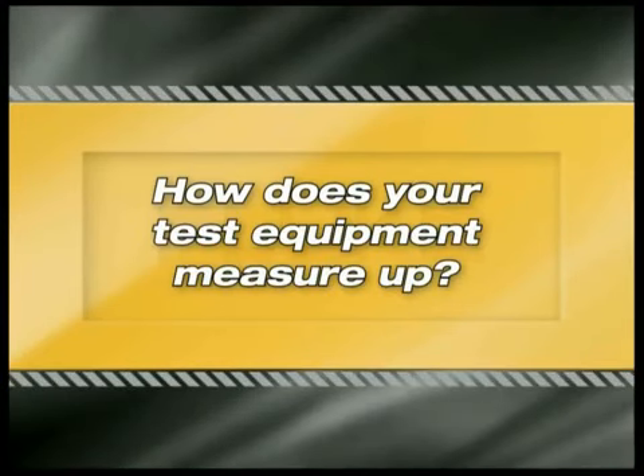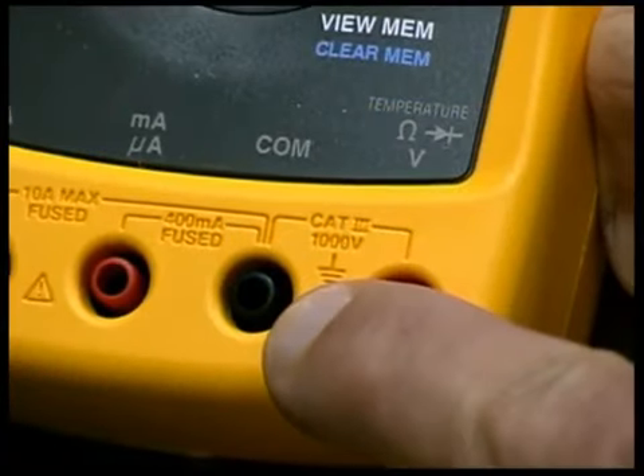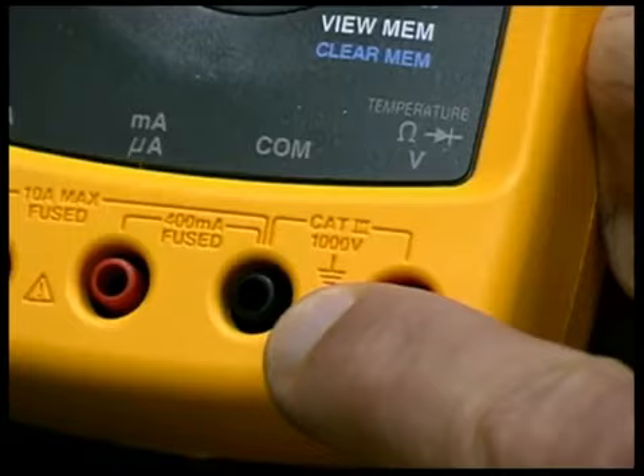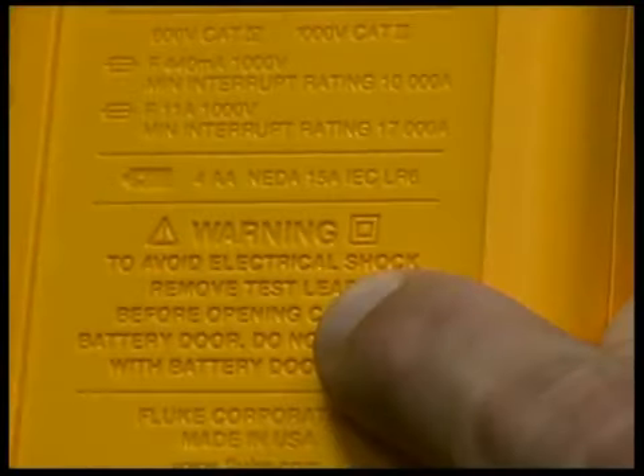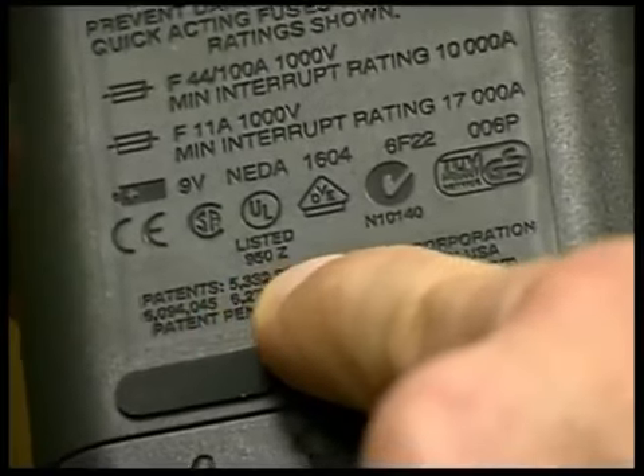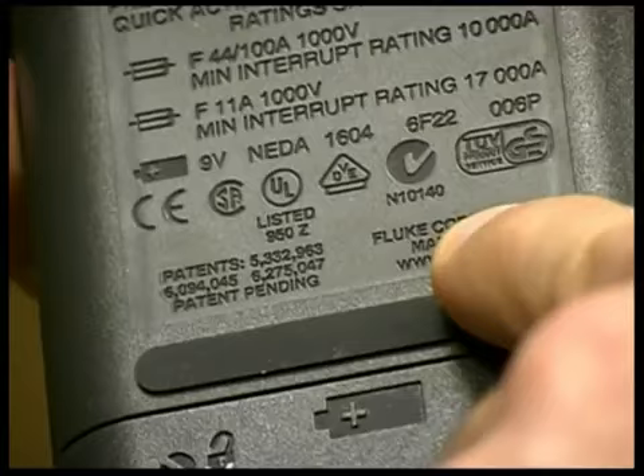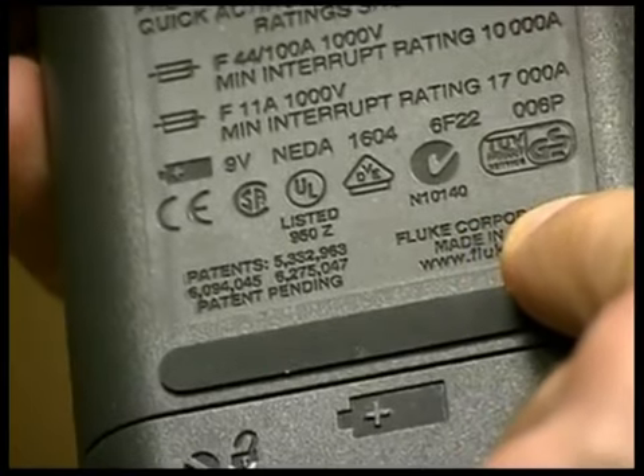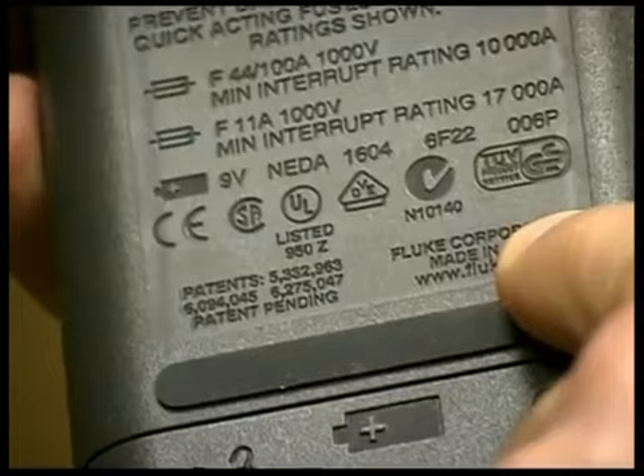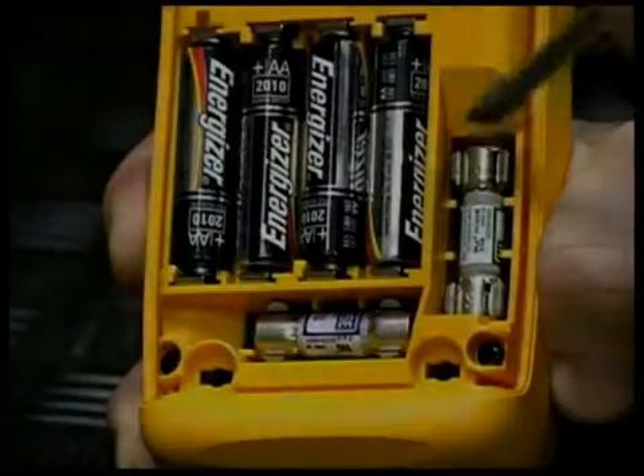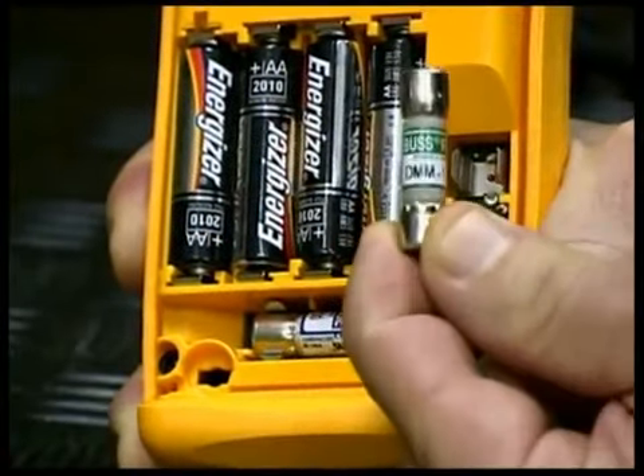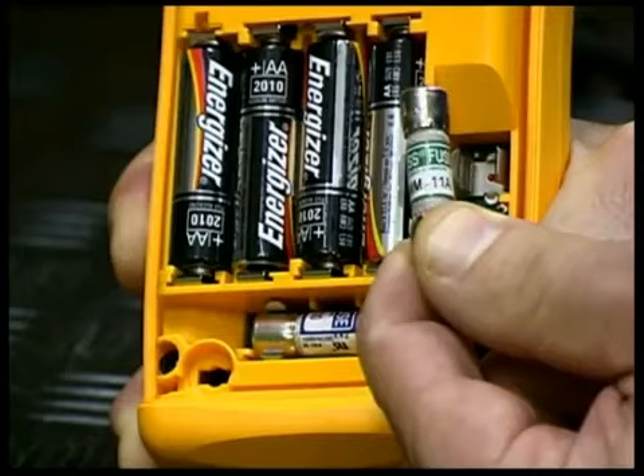How does your test equipment measure up? Here are tips for inspecting your own equipment. Look for the Cat 3 or Cat 4 rating on the front and a double insulated symbol on the back. Look for approval symbols from 2 or more independent testing agencies, such as UL, VDE, or TUV. Check the meter fuses for the correct amperage and voltage. Fuse voltage must equal or exceed the meter's voltage rating.